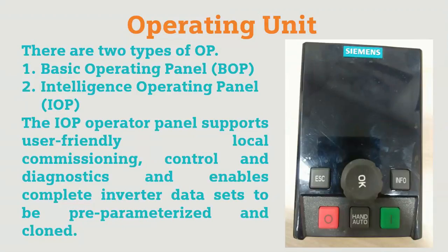There are basically two types of operating unit: the basic operating panel and the intelligence operating panel. This picture shows the intelligence operating panel. The IOP supports user-friendly local commissioning — in a very short time you can commission, control, or diagnose the complete inverter data set, and save the data in the drive. Different buttons allow you to insert parameterization data and save it to memory. For the Siemens series, you can save data onto a memory card and then use it in another drive.